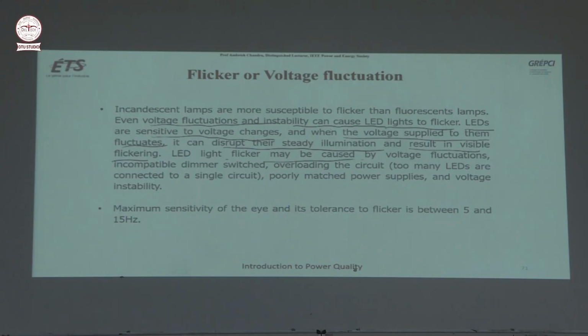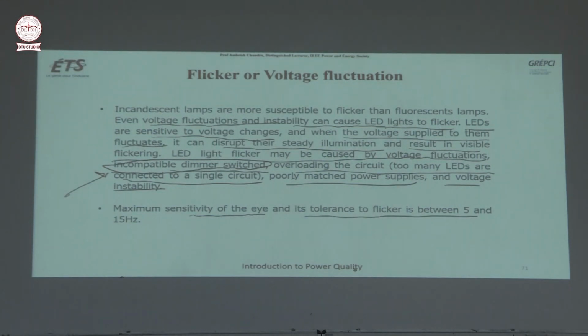LED light flicker may be caused by voltage fluctuation or an incompatible dimmer switch. So in my case, in Canada we don't have voltage fluctuations, but then I realized the dimmer I bought from somewhere else and the lamp bulb I bought somewhere else, perhaps they were not compatible at a certain limit. So an incompatible dimmer switch may cause it. Overloading of the circuit, too many loads connected to a single circuit, poorly matched power supplies and voltage instability may also cause this. Maximum sensitivity of the eye and its tolerance to flicker is between 5 and 15 Hz.